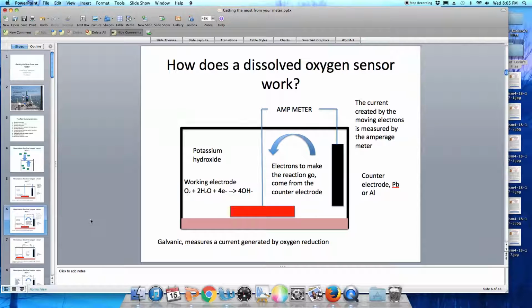So how does a galvanic dissolved oxygen sensor work? The dissolved oxygen migrates through this permeable membrane into the electrolyte solution, in this case, again, potassium hydroxide. And at the working electrode, we add 4 electrons to the oxygen molecule. This is the dissolved oxygen molecule, and with some water reacts to produce 4 hydroxide ions. So we're adding electrons to the dissolved oxygen molecule, or we are reducing it, as the chemist would say.